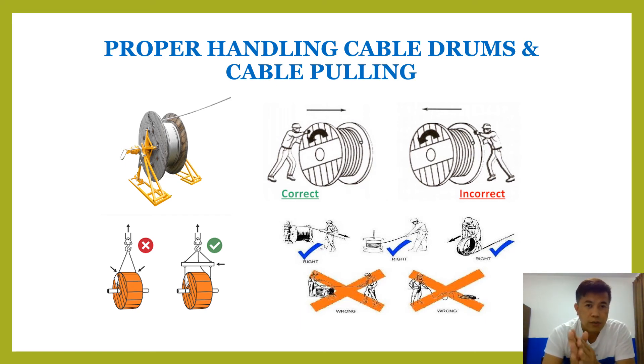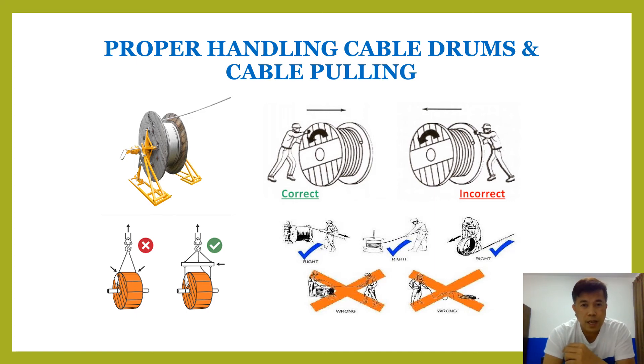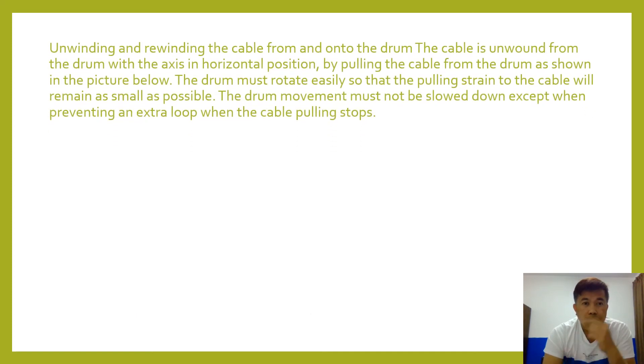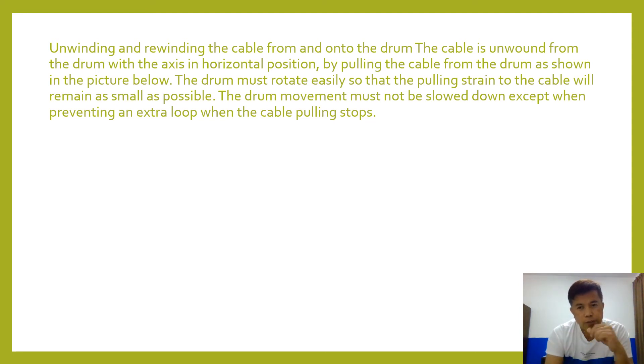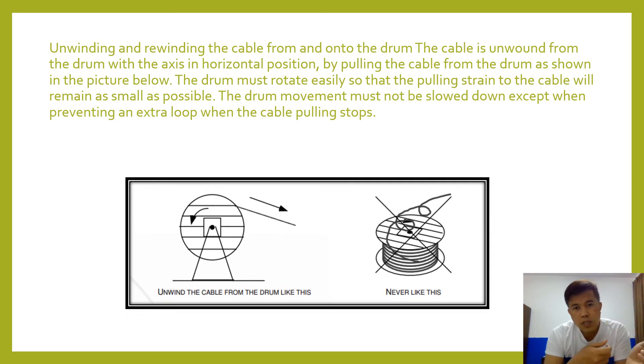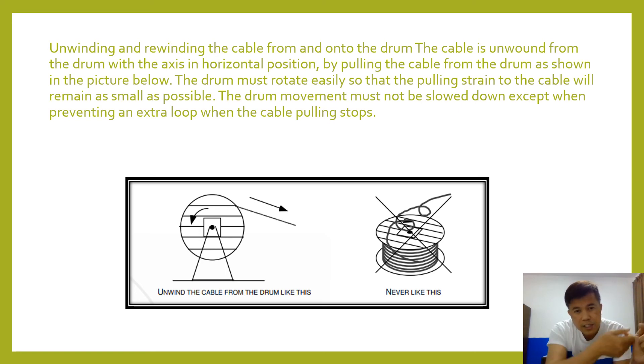This is how it looks — you can see the differences and apply them in your construction. If you are a foreman, supervisor, engineer, or inspector, you can see what the difference is on site. When unwinding the cable from the drum, there is an arrow when purchasing the cable that shows how it is coiled inside the drum. When you are unwinding the cable drum, you can see the arrow sign and this is how you pull the cable — don't do it from the wrong side.